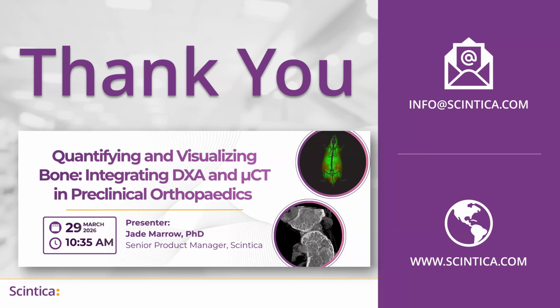The next one is, could you comment on continuity of evaluation between different users? Yes, absolutely. DEXA is a very good method in a sense that the analysis itself is not affected that much by the users. When you have those images, like the example of the mouse I showed here, different users can use the same ROI boxes to analyze the different bones. One thing that is really important to consider, and that you cannot change after the study has been completed, is the positioning of the mice for imaging.